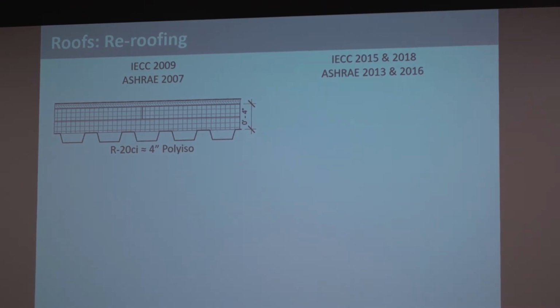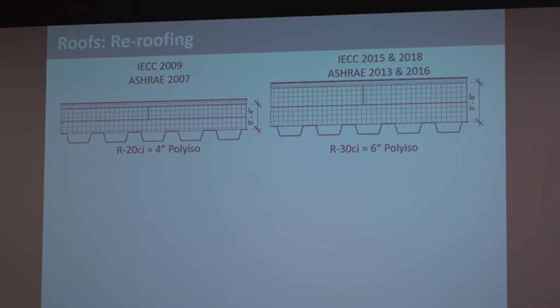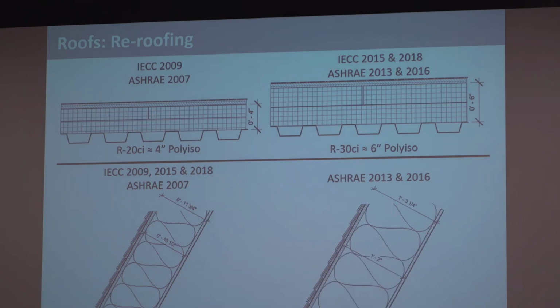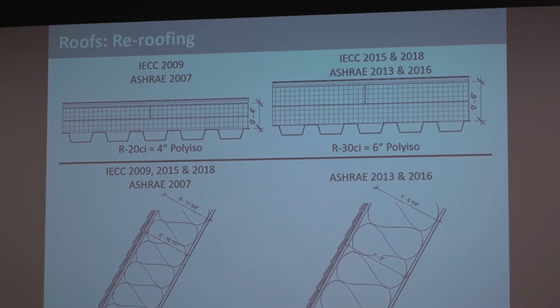So what does this mean? We went from R20 CI, which was 4 inches, to R30 CI, which is 6 inches. For most commercial construction, this isn't a big deal. It might change some of your parapet and flashing details. Maybe your dunnage and things have to get a little bit higher, but for the most part in new construction on flat roofs, this is not that big of a change. I mentioned that ASHRAE 2016 changed to R49 batts. That's going to change framing and insulation requirements below sheathing quite a bit. And like I said, once we see some changes start to happen in one version of the code, we often see that start to happen in subsequent versions of the other code. So this is potentially something we're going to start to see happen. And yes, there are R49 batts on the market. It's just changes in how you're going to frame out that roof assembly.